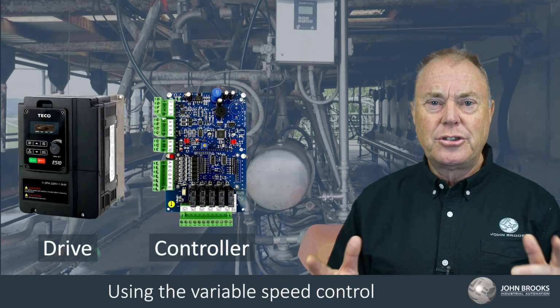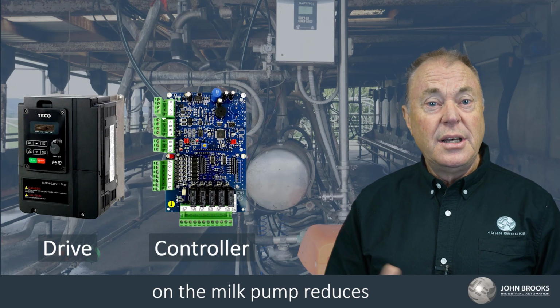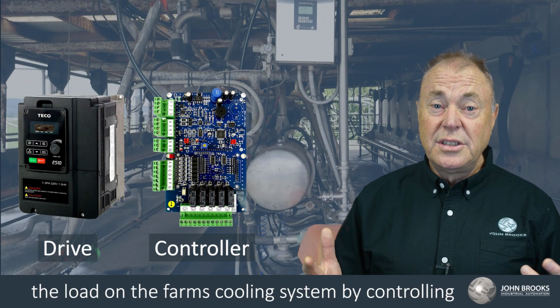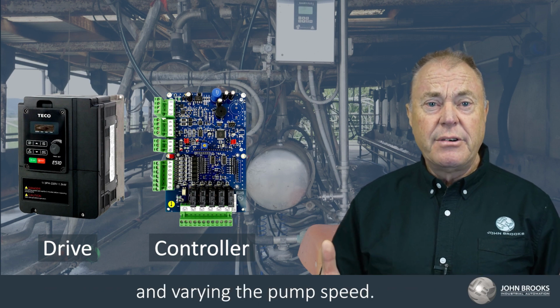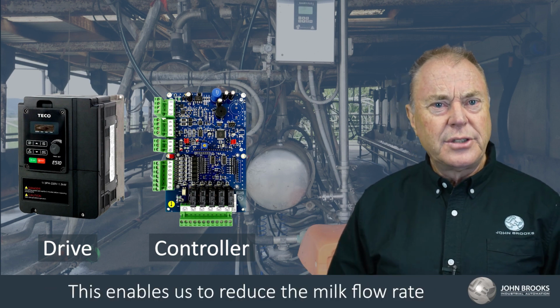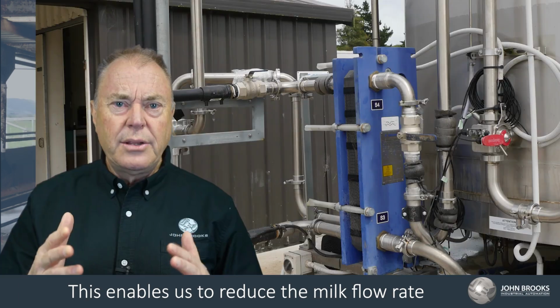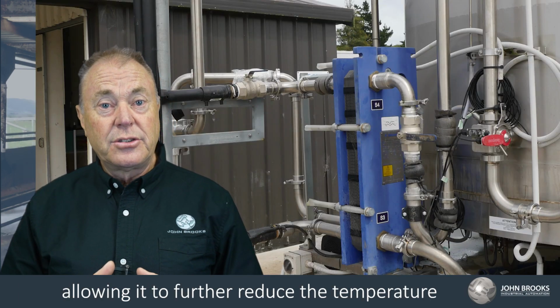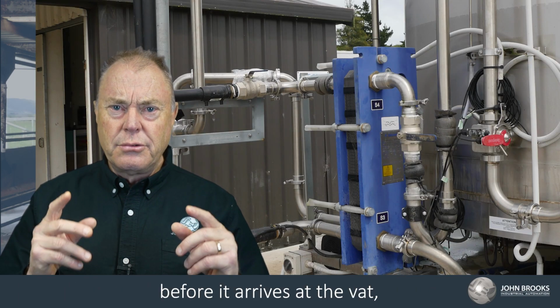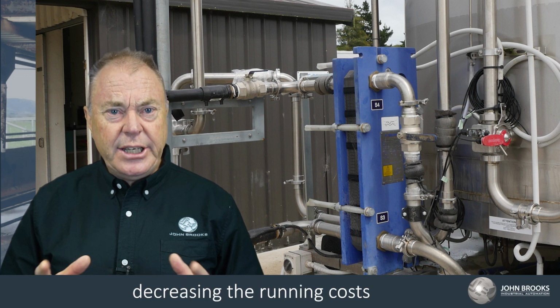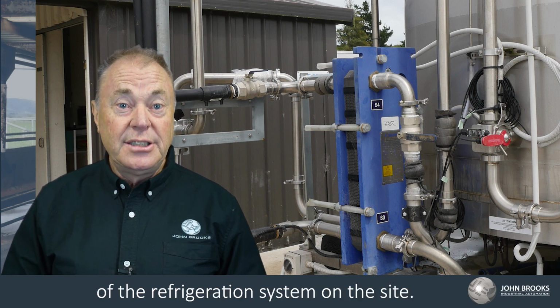Using the variable speed control on the milk pump reduces the load on the farm's cooling system by controlling and varying the pump speed. This enables us to reduce the milk's flow rate through the heat exchanger, allowing it to further reduce the temperature before it arrives at the vat, decreasing the running costs of the refrigeration system on the site.